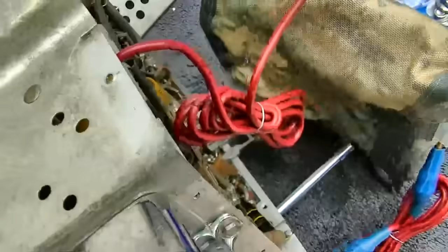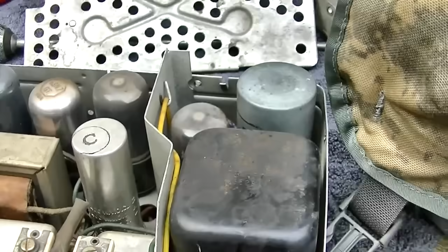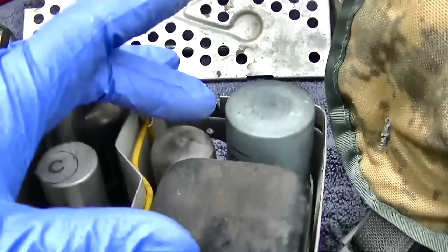It just stopped vibrating. Okay, so here's what's happening. I took this apart again and cleaned it, and the contacts were quite burnt. Then I fired it up and listened real close, and I could hear it buzzing, and then after 20 or 30 seconds when the rectifier started warming up, I could hear it start arcing, like 60 hertz arcing, and then it locked. So something, I have a feeling...